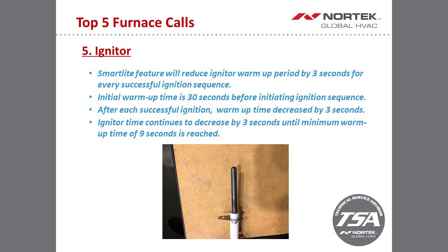Now, if you kill power to the furnace and reapply power, let's say if you had a 1-hour lockout code, that is going to reset the 30-second warm-up time. So you'll go back to 30 seconds, and then after each successful ignition, it will work its way back down all the way to 9 seconds. So if you kill power and reapply it, you'll end up resetting the Smartlite feature.